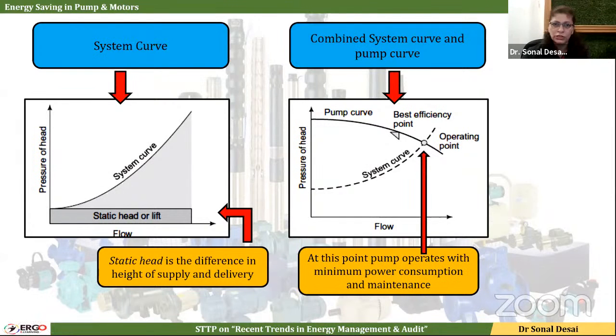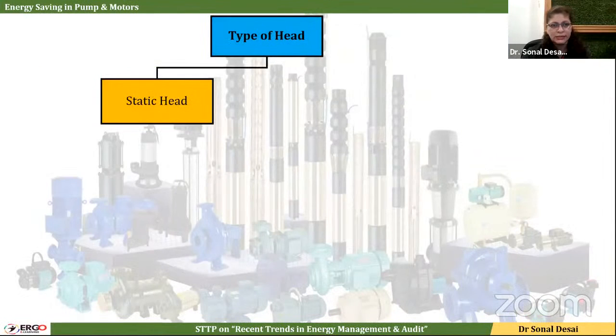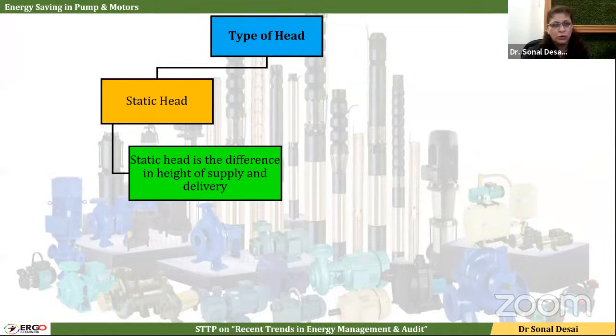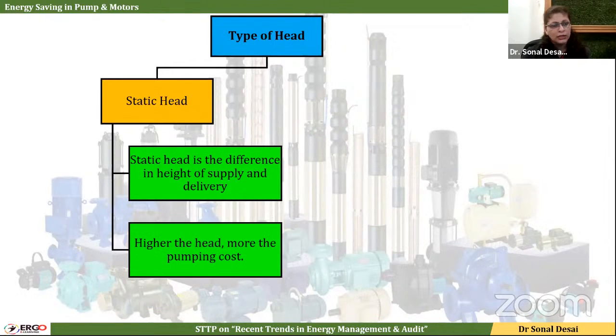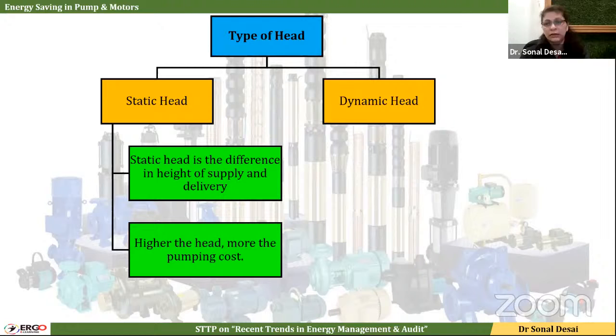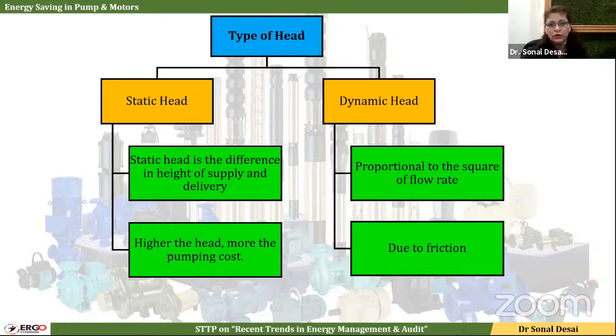It is good to operate the pump at this particular range. We will talk on those slides later. First, let us have a look at what head is. Head is basically the amount of head that is created by the pump. When we talk of static head, that is the difference of height between supply and the delivery. And when we talk of dynamic head, it is how much friction the pump is able to handle.